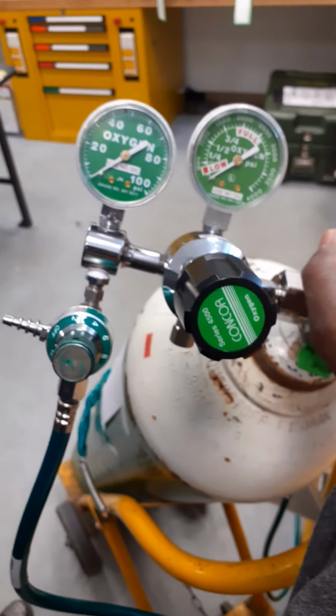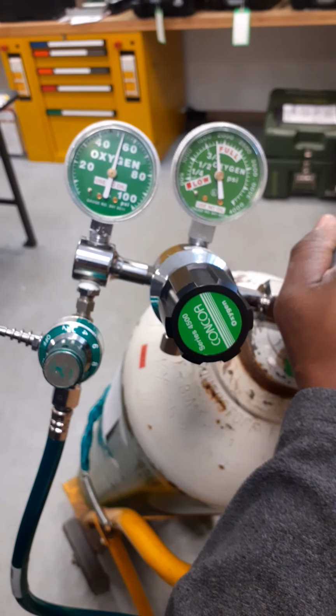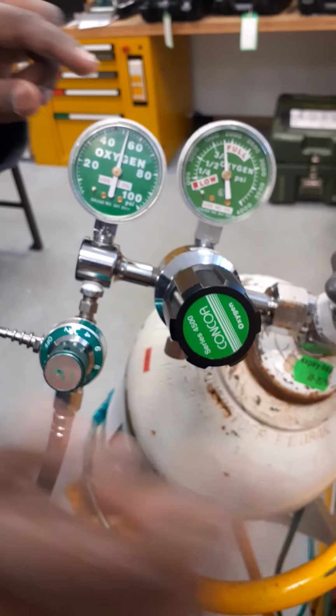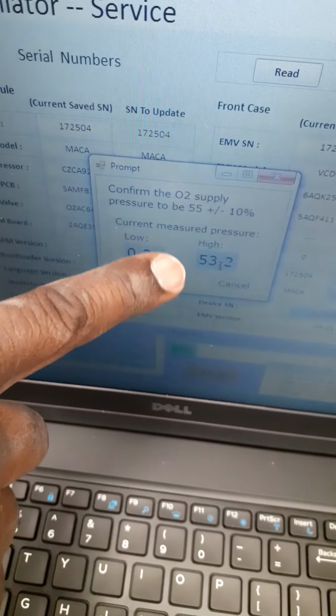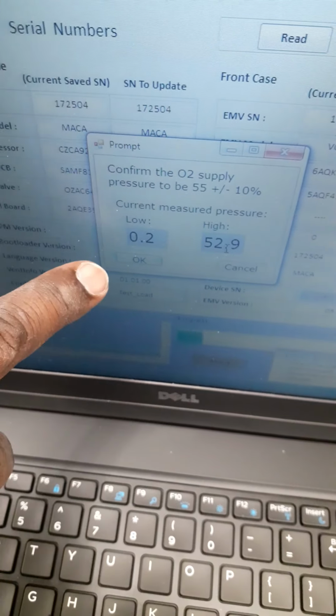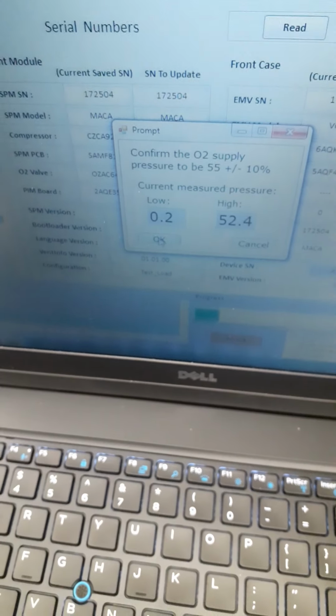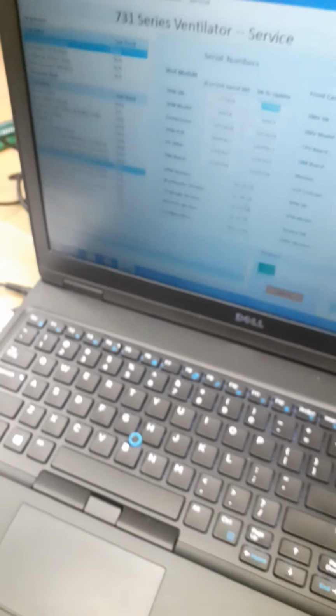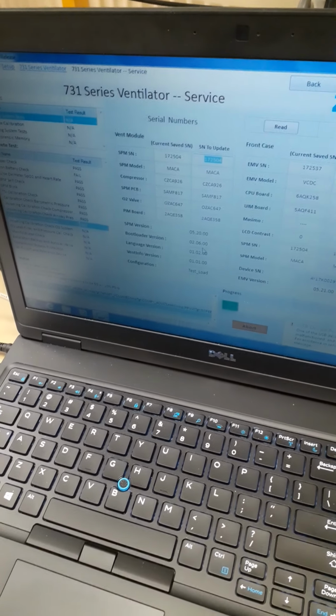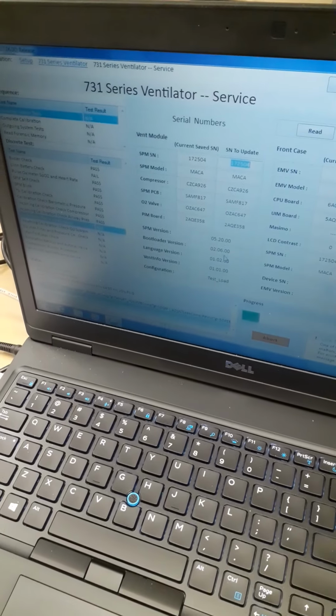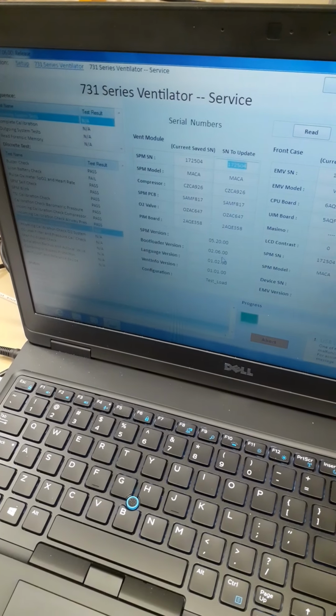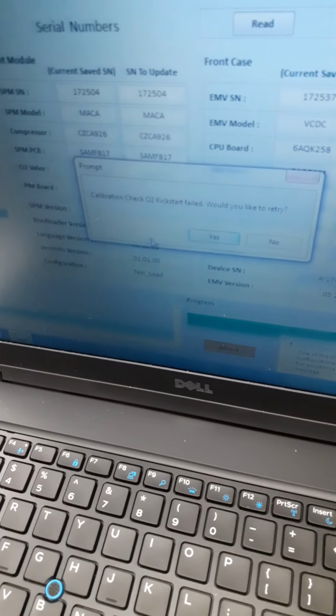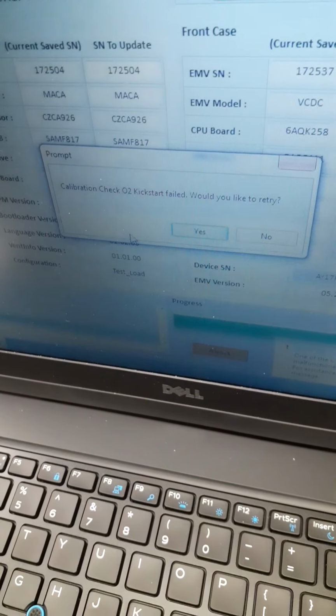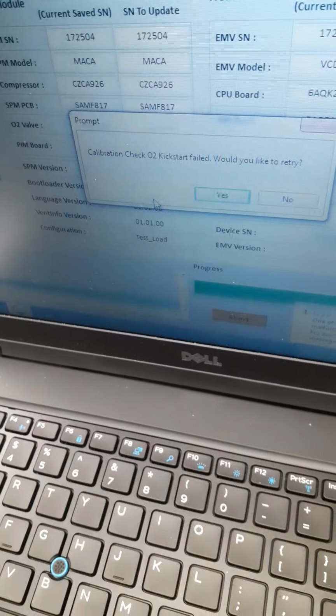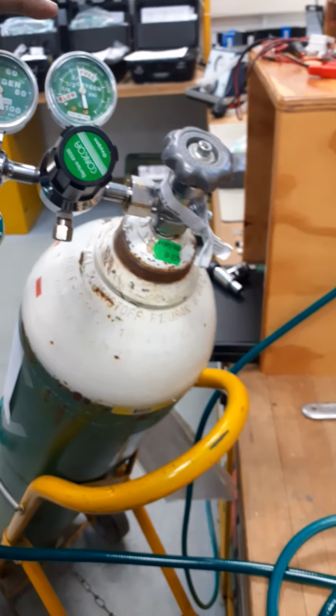So let me go ahead and turn this on. Gauge is a little off, but we'll be able to tell by what's showing up here what we have. So yeah, 55 plus or minus 10%, that falls within the range. It gives us an okay. If it was outside of the range, this would be gray and you wouldn't be able to activate it. Okay, so it told me it failed the kickstart. Let me add a little bit more pressure. I didn't wait long enough for it to stabilize. That could be the issue.